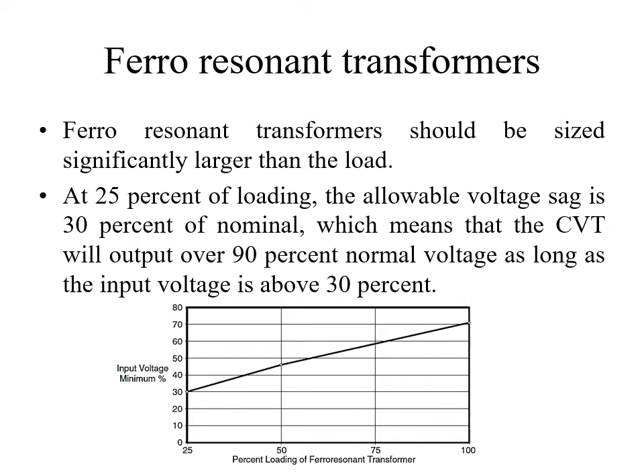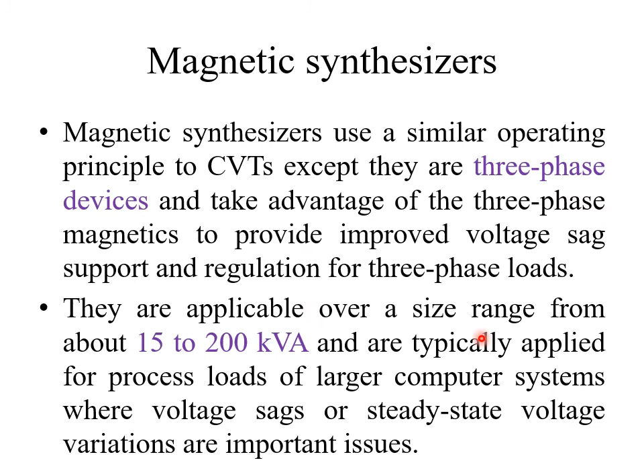Magnetic synthesizers. Magnetic synthesizers use a similar operating principle to ferroresonant transformers or CVT. The only difference is that ferroresonant transformers are used for single phase or low power applications, whereas magnetic synthesizers are used for three phase devices or high power applications. So they will be mostly found in industries, where the sizes range from 15 to 200 kVA.